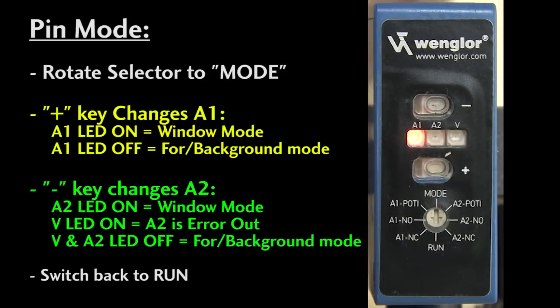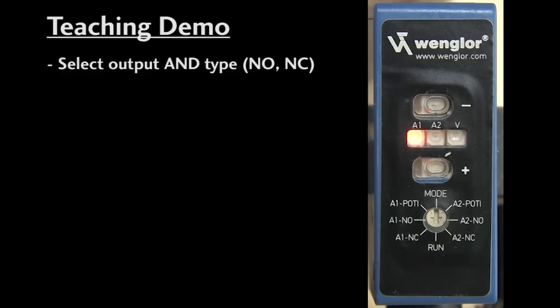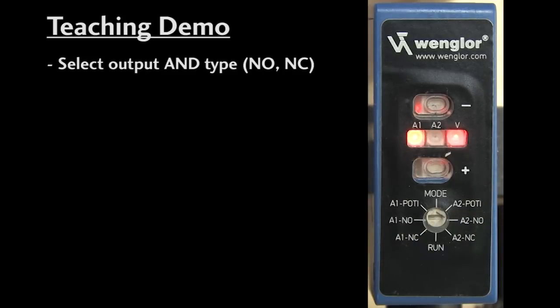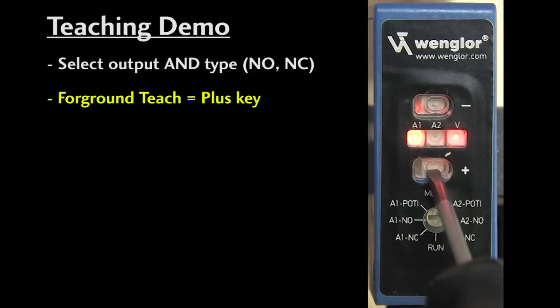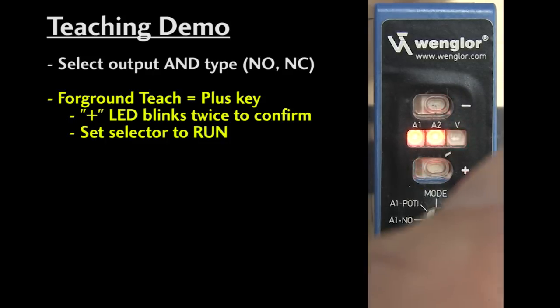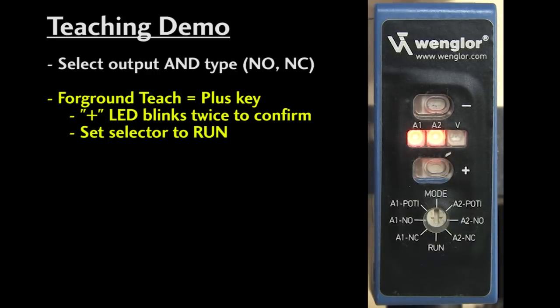Once you've selected the mode, now you teach it by selecting the output AND the type – normally open or normally closed. We set A2 to be foreground background mode in step 1. To teach it as a foreground object detector, just point the laser at the object you want to detect and press the plus key. The plus LED will blink twice to confirm. Set the selector back to run and now any object that comes closer than that distance will activate pin A2.